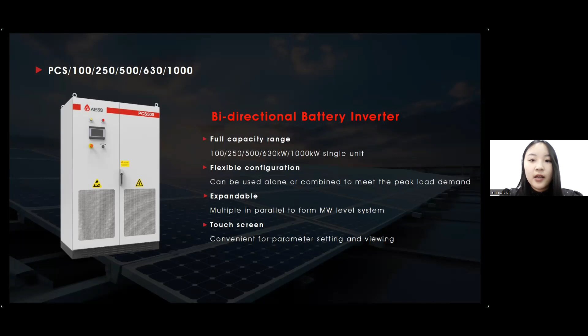And the next page is about the isolation transformer I kept talking about. PCS inverters for large-scale systems must be equipped with an isolation transformer. Why is that? Because it can provide a neutral N-line for the AC side, eliminate harmonic waves, and improve safety and protection. The isolation transformer of PCS 100 and 250 is built in this cabinet. But for the other three models, PCS 500, PCS 630, and PCS 1000, the cabinet is already very big. So the isolation transformers are internally wired and externally installed.